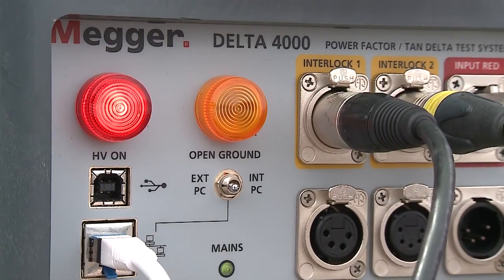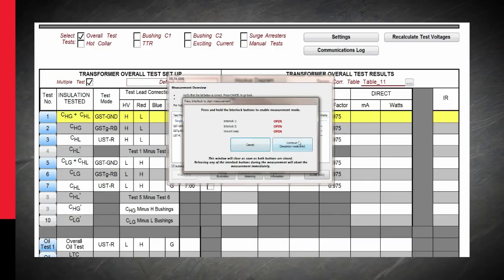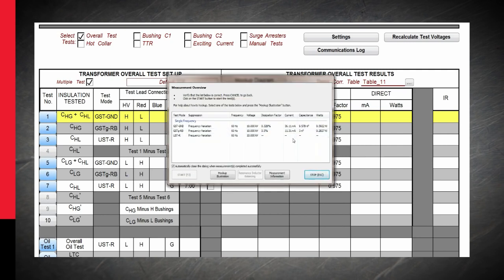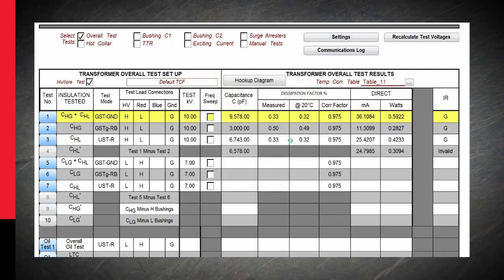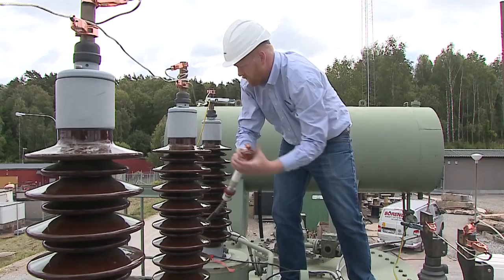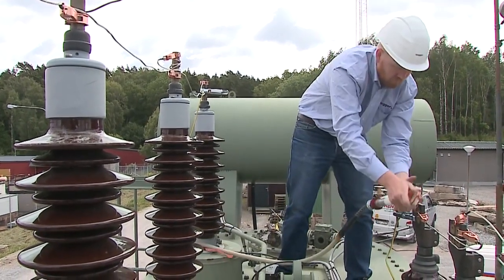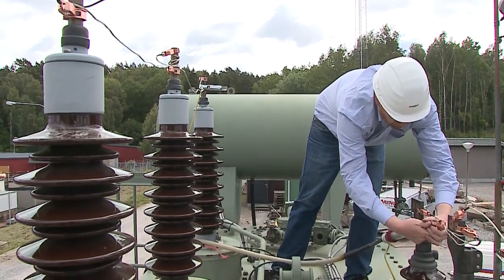Once interlocks are depressed, voltage is applied to winding and tests are executed. We can now observe testing as it is automatically completed, noting any unexpected results. We review the results and determine if they are acceptable. We are now ready to test the low voltage portion of the transformer.